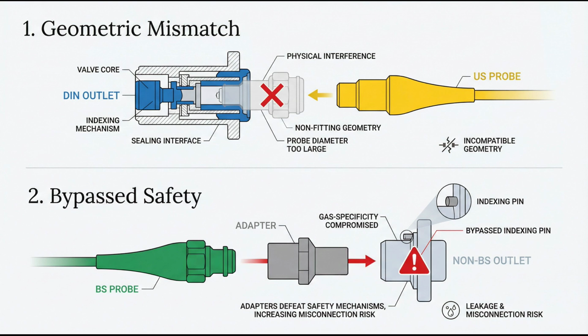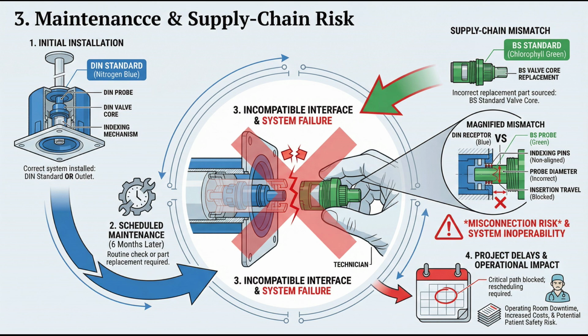The first pitfall is simple. The parts don't fit. A more dangerous risk emerges when adapters create a false fit, bypassing the safety logic that prevents giving a patient the wrong gas. But the danger also extends over time. Months after installation, a simple part needs replacing, but the hospital supply chain is based on a different standard. A critical room is now offline, crippled by a single, incompatible, low-cost part, creating immense operational risk.